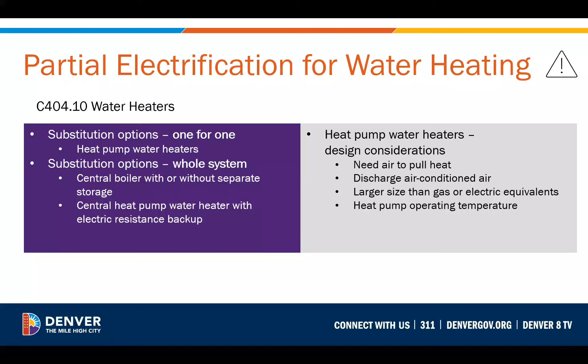Anytime though we're talking about heat pump water heaters, it is really important to consider all the different design constraints. When you're introducing a heat pump, it needs to pull heat from somewhere, so it needs air to pull that heat from, and then it's going to discharge that air much colder, in like an air conditioned state. So you need to be accommodating that. They're also larger. You have that whole refrigeration cycle within the unit, so they're bigger than a traditional gas or electric resistance water heater. And then you also need to consider the heat pump operating temperature. The heat pump might turn off at a certain temperature, not be able to pull heat from the outside air, so you need that electric resistance backup to still provide domestic hot water during those times.